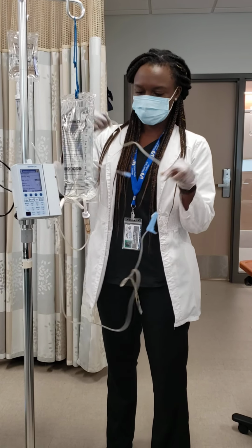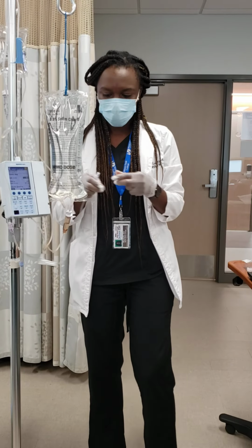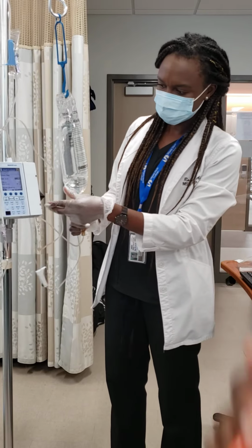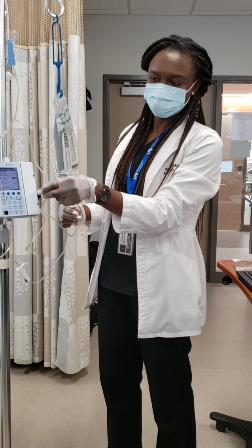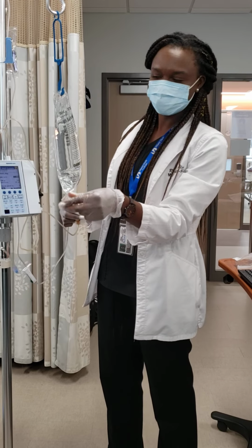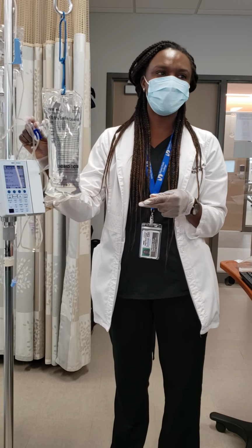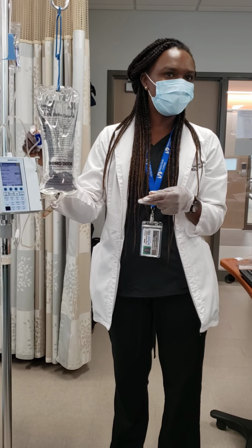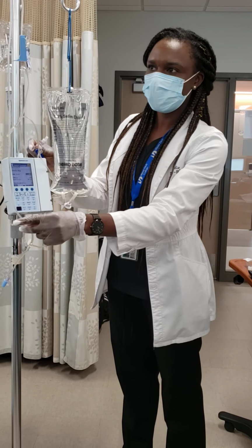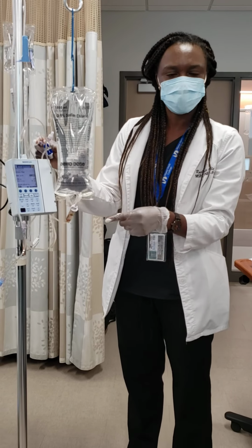I like to just hang this up here to get it out of the way. All right, so this is the primary line. Where do you think I hang it? And the little thing connecting to the port, the first one, the first primary. This primary one here? Yeah. The closer to the pump, as they see in the video. You have to hang it above the pump. Why?